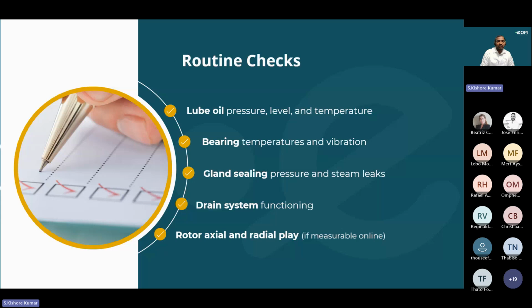And coming to the drain system, in a lot of plants, they never look at the drain systems, because in some plants the drains are directed to the condenser in a closed loop, so there is no chance to check. This leads to some of the drains being clogged or choked, so the condensate water does not pass through the drain systems, and it accumulates in the turbine casings, and it may cause damage to the turbine and also the blades. So always ensure the drain system is working properly.